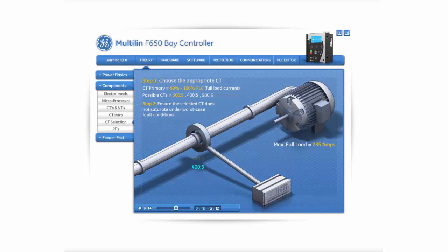The first step in determining whether a CT will saturate is calculating the maximum voltage that will appear on the secondary of the CT under a worst-case fault condition. The maximum fault current at the load is determined by a fault study, and in this case was determined to be 6,000 amps. Next, we will calculate the secondary resistance, or burden, using the stats provided.